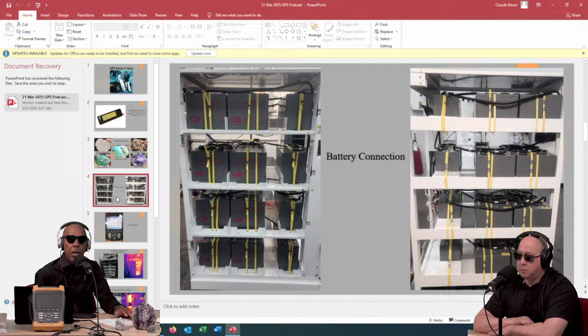One of the first things we do outside of wiring it up is the whole torquing process on the terminals - we make sure they're properly torqued. This torque wrench is what we actually use to make sure the batteries are at the correct spec. There were 40 batteries on this, with 2 terminals per battery, torqued to 44.9 spec. The reason that's so important is you don't want heat - heat is energy loss across the cells, so making sure they're torqued to the correct spec is imperative.